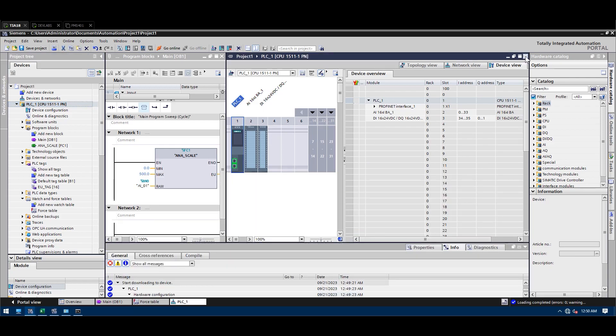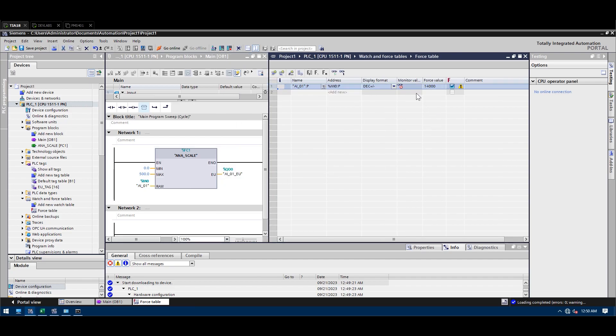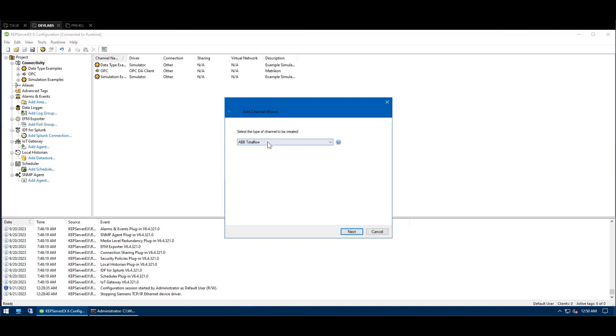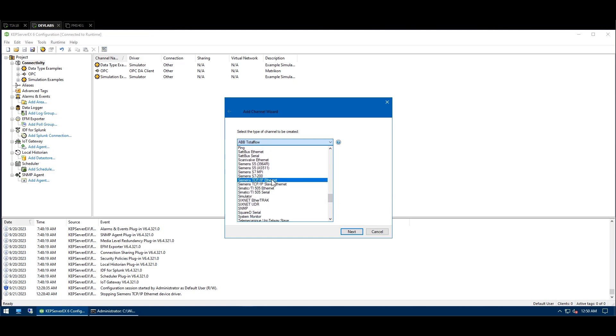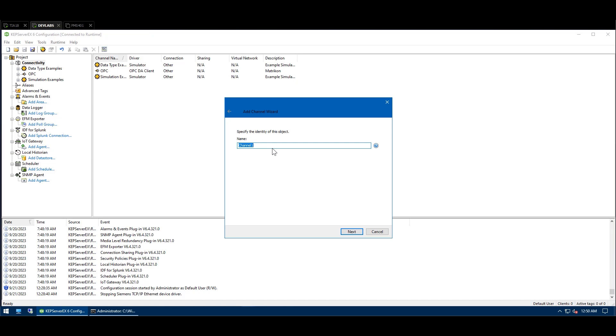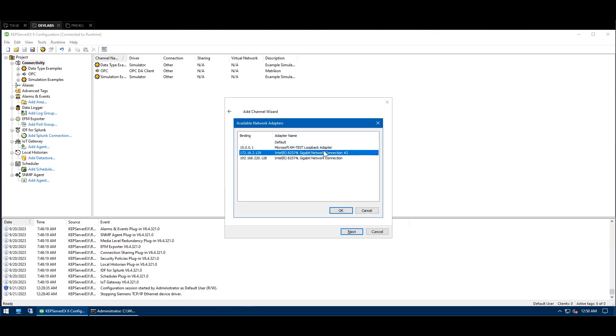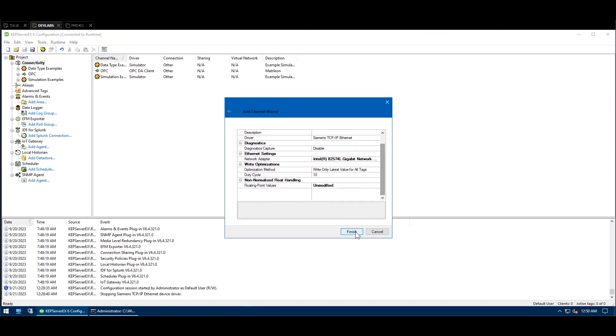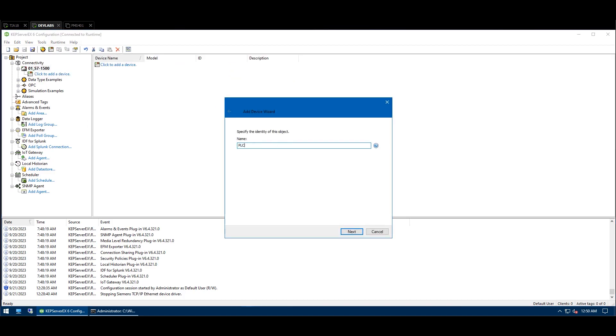I'll close this and go back to the other tool just to make sure our data is coming through to the other side. I'm going to connect using Siemens TCP Ethernet — I'll call it 'S7-1500'. I'll choose IP 172.18.2.129, click Next, leave unmodified, and Done. Now I'll add the PLC and put in the PLC's IP address.